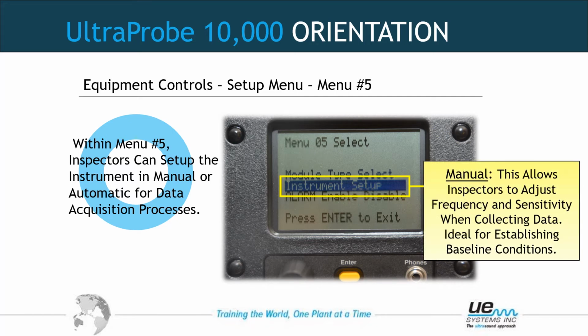Rotate to menu number 5. Menu number 5 is instrument setup. This is fairly important. Instrument setup is either manual or automatic. If we were in the automatic mode and you enter this item, again by pushing the sensitivity dial, the default is manual setup. If you're in the automatic mode, you would have baselined a route, taken all the readings, say it was a bearing route, certain frequency, certain sensitivity at every different position, as well as any record information that you inputted. All that information is on the baseline.